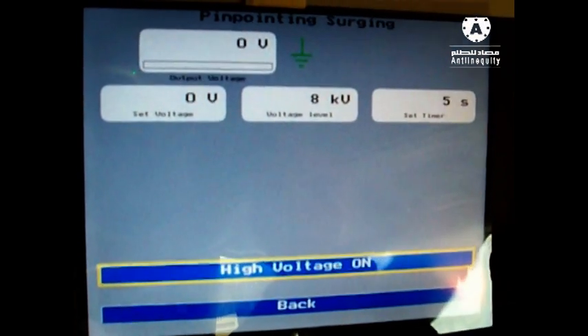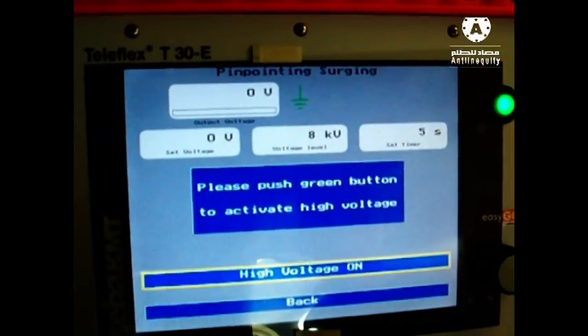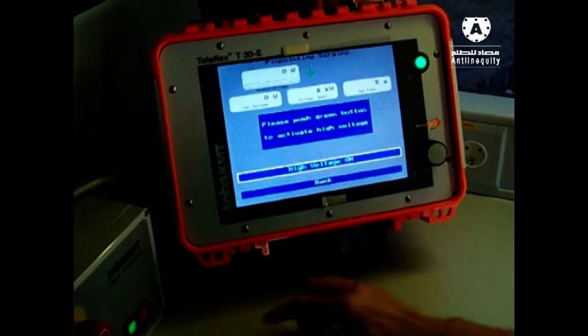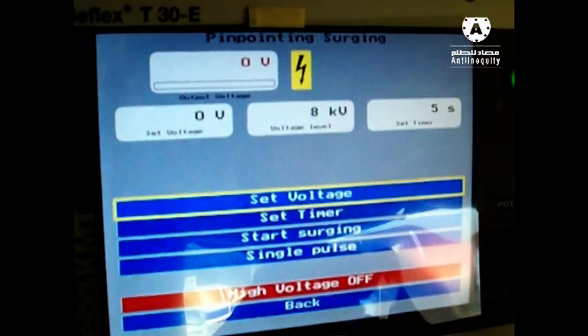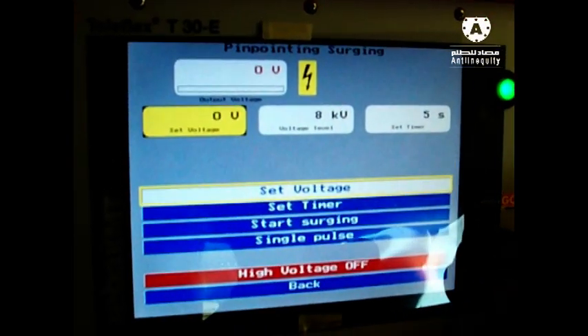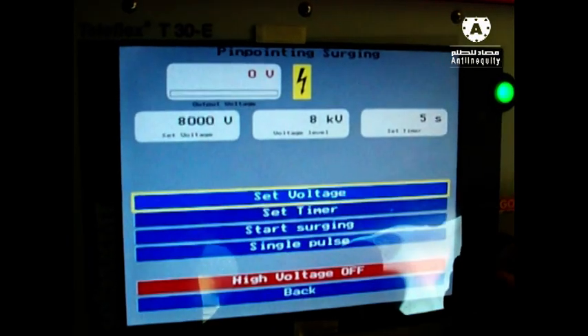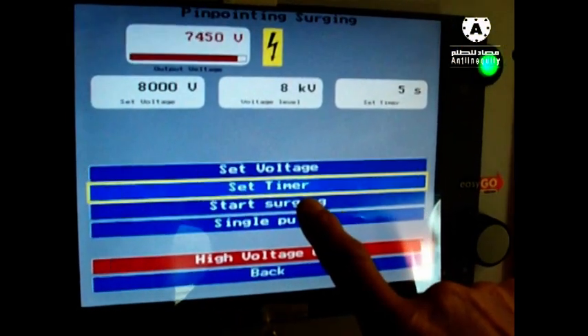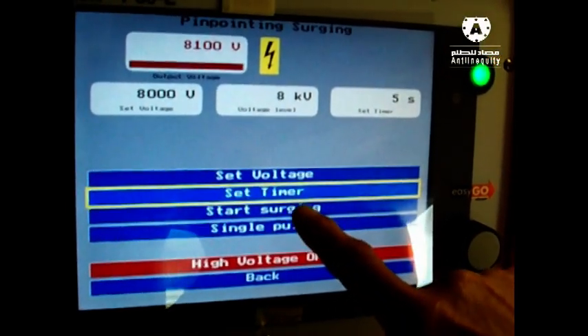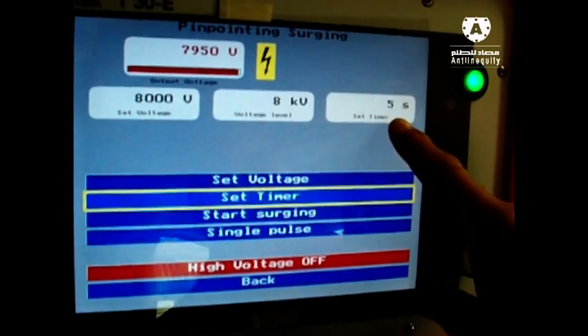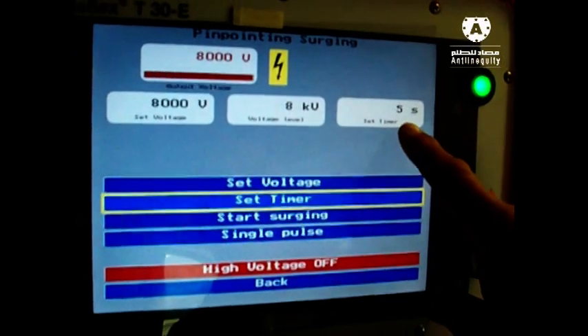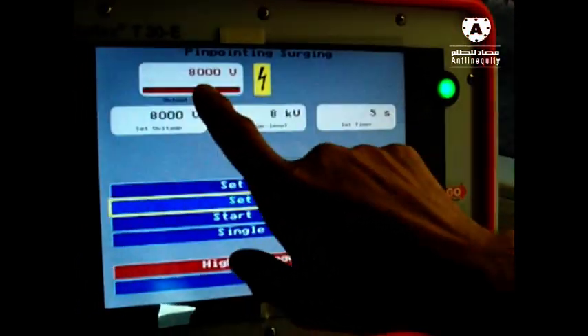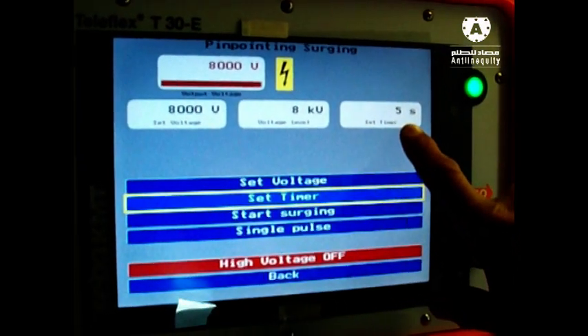Do the same now. High voltage on, the green button. System is preparing now. Okay. You see, red light is on, high voltage. In the first, we can select now our set voltage. We say 8 kV. The second is we set our timer. Timer means we have an automatic or manual mode. In automatic mode, this is the time delay between the shots. So it's 5 seconds. In this special case, to reach the maximum value, we must adjust this to 6 or 7 seconds.